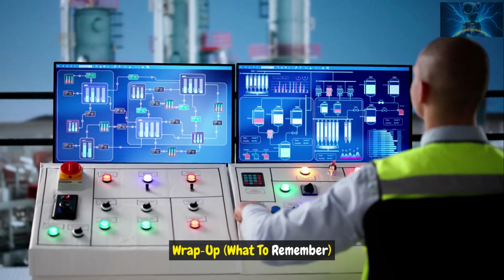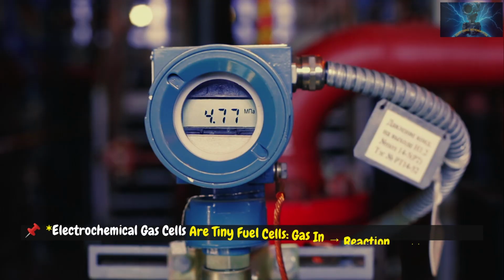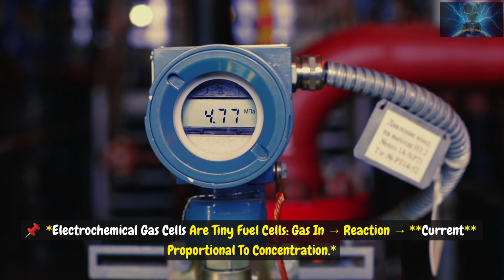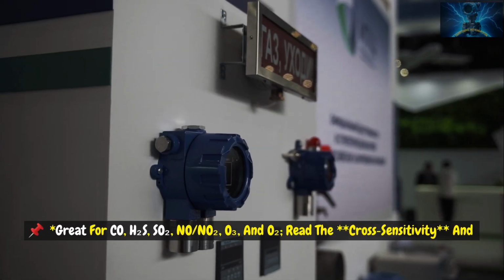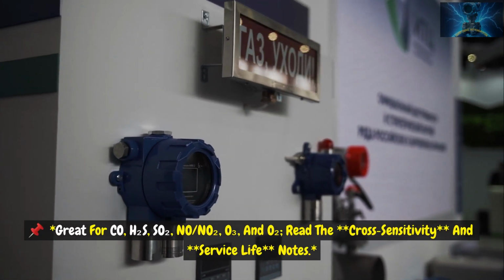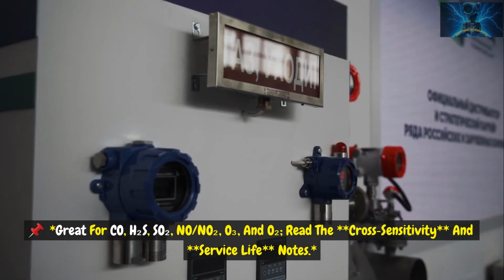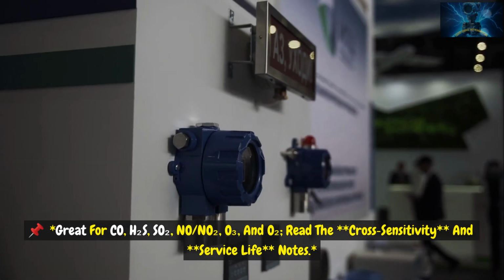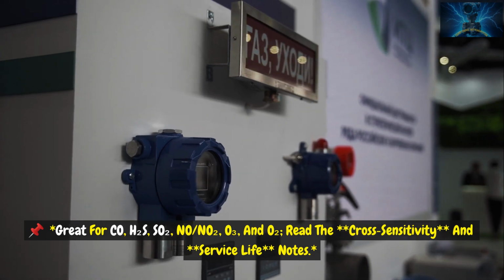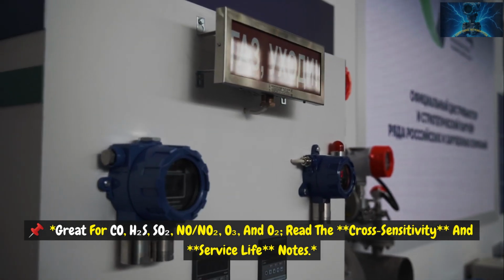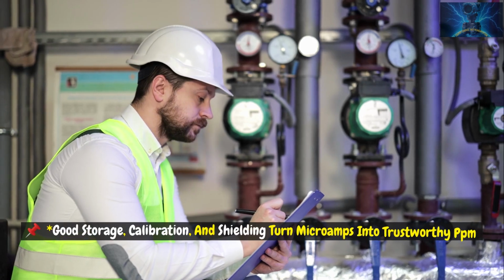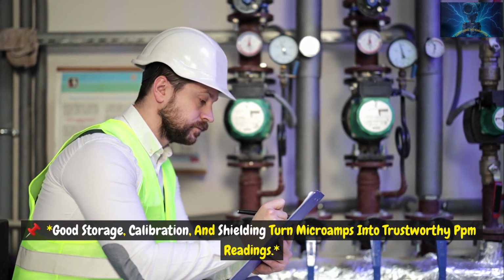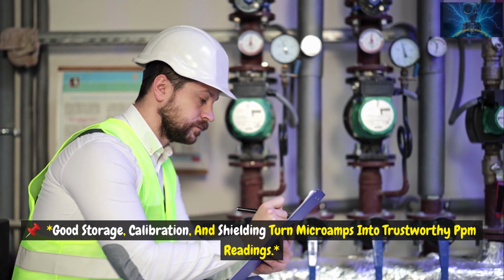Wrap-up, what to remember. Electrochemical gas cells are tiny fuel cells: gas in, reaction, current proportional to concentration. Great for CO, H2S, SO2, NO2, O3, and O2. Read the cross-sensitivity and service life notes. Good storage, calibration, and shielding turn microamps into trustworthy ppm readings.